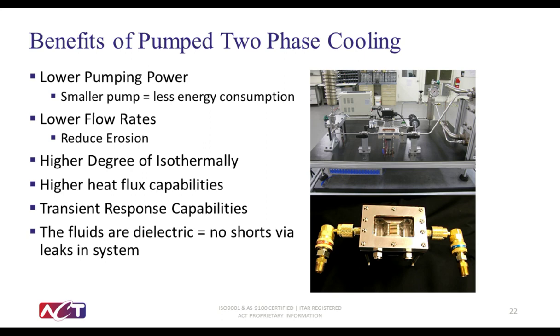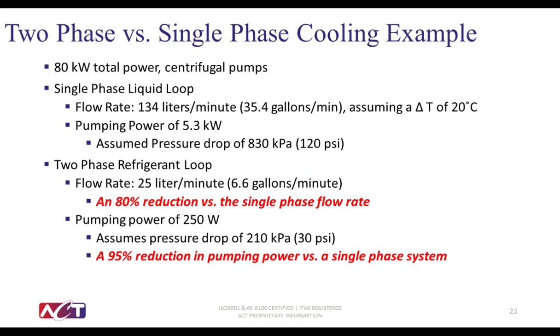Additionally, it has higher heat flux capabilities. 300 up to even 1,000 watts per centimeter squared results have been reported. It has good transient response capabilities. We'll show a video of that too, and the simplified control system. Although P2P systems can use water or ethylene glycol, most often they use refrigerant. These fluids are dielectric and ensure there are no shorts via leaks in the system.